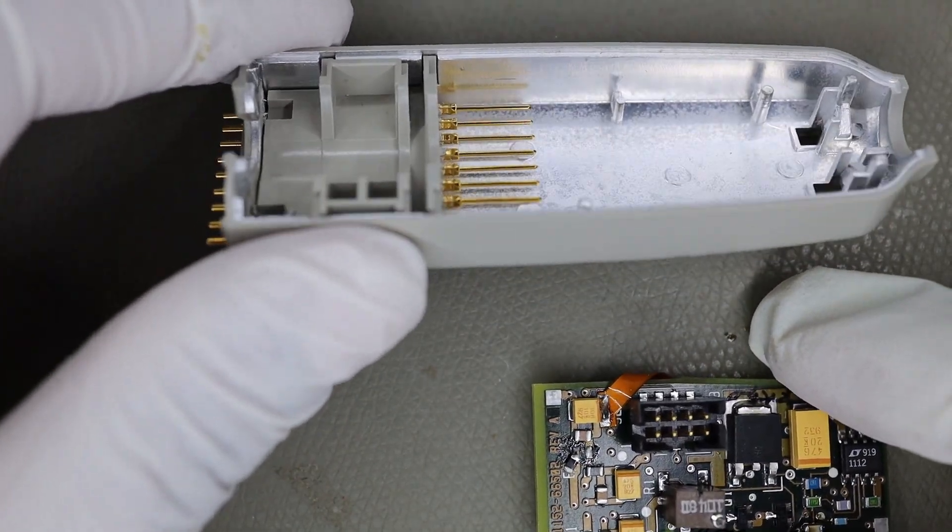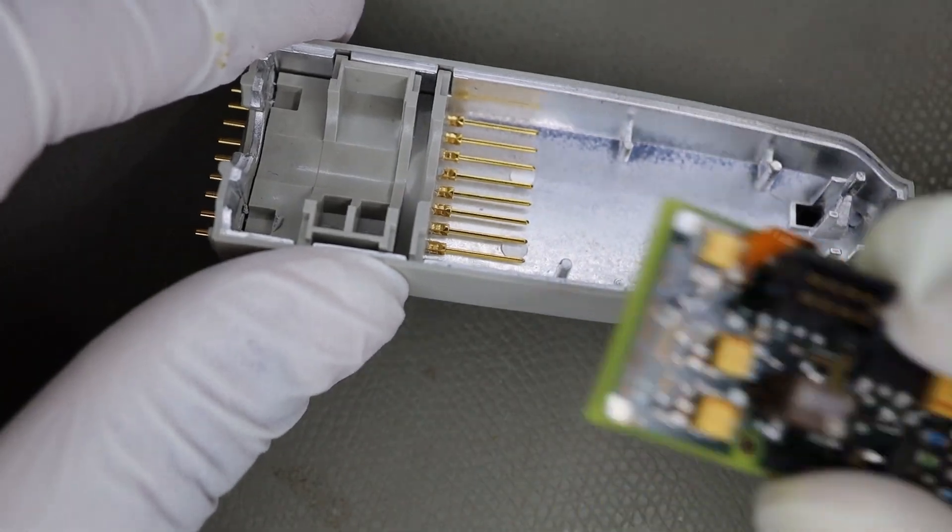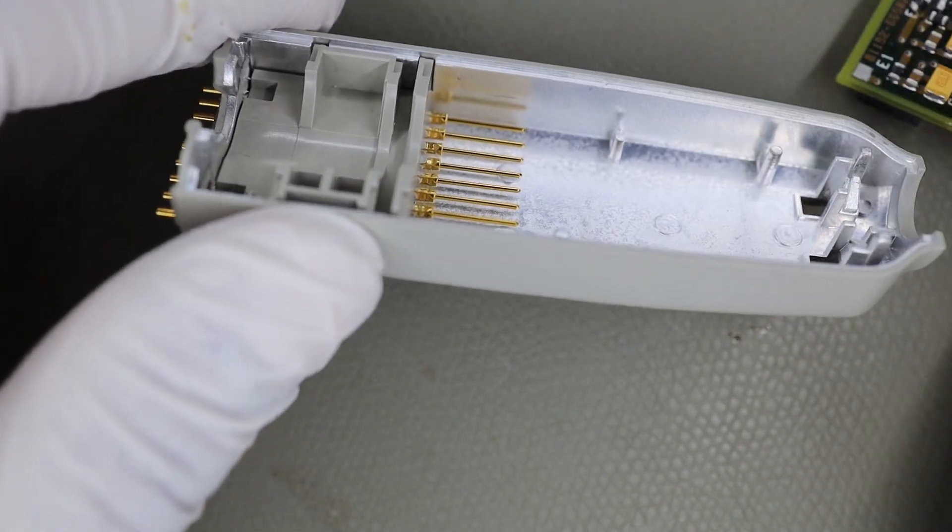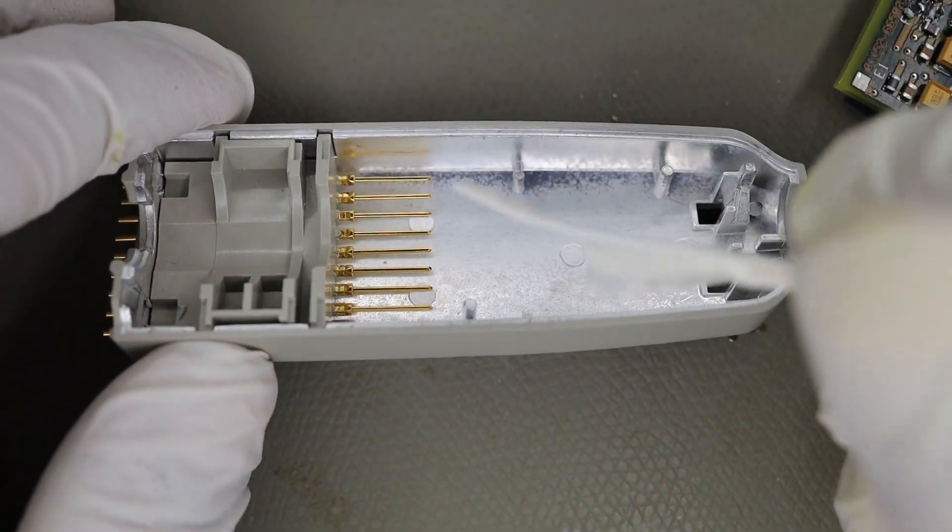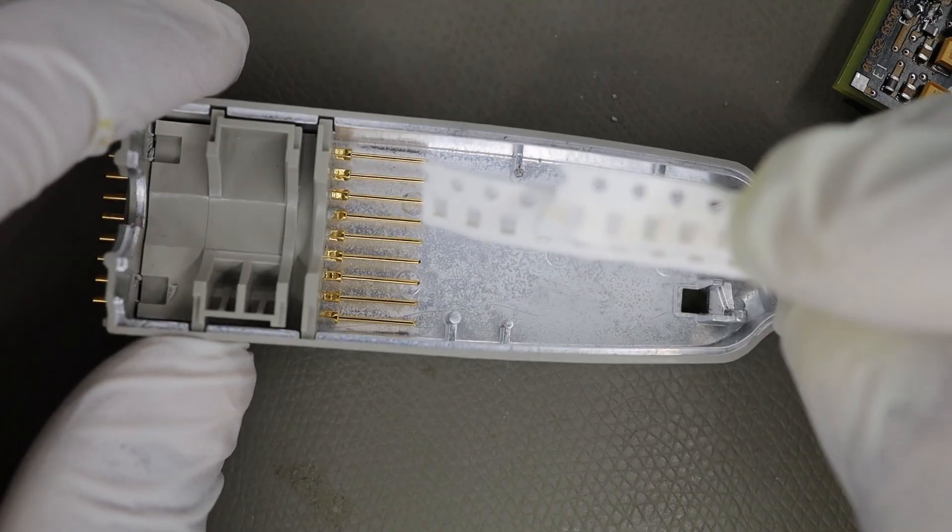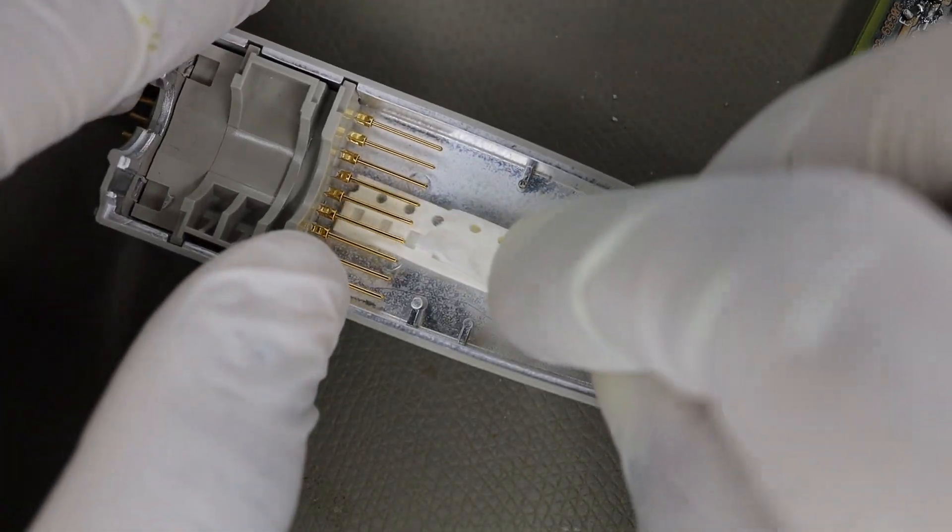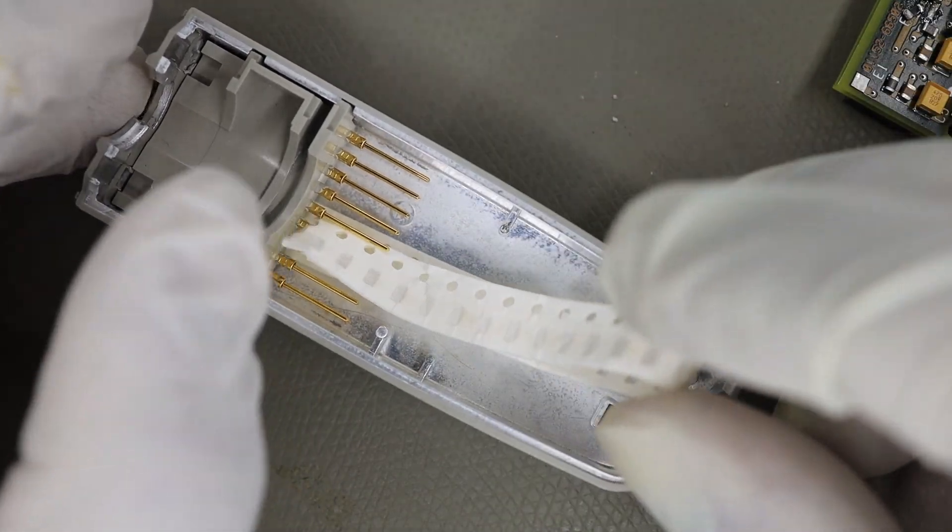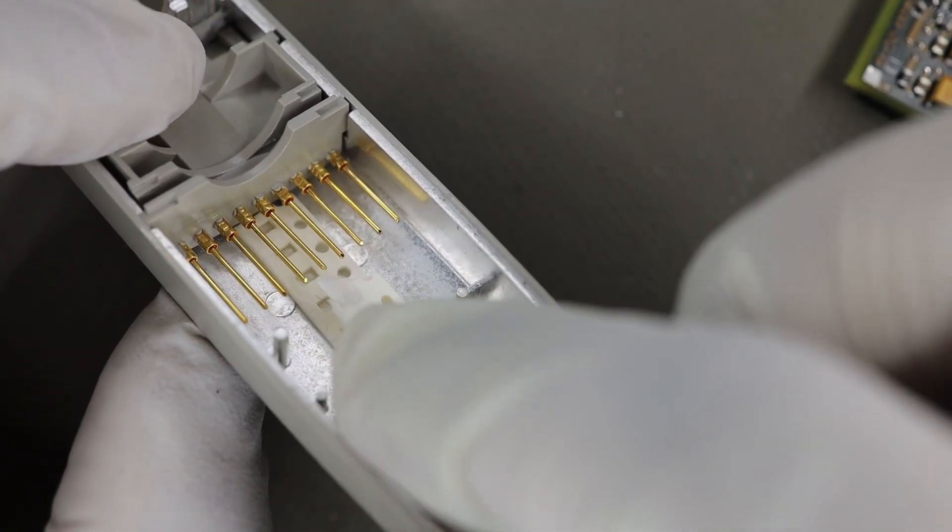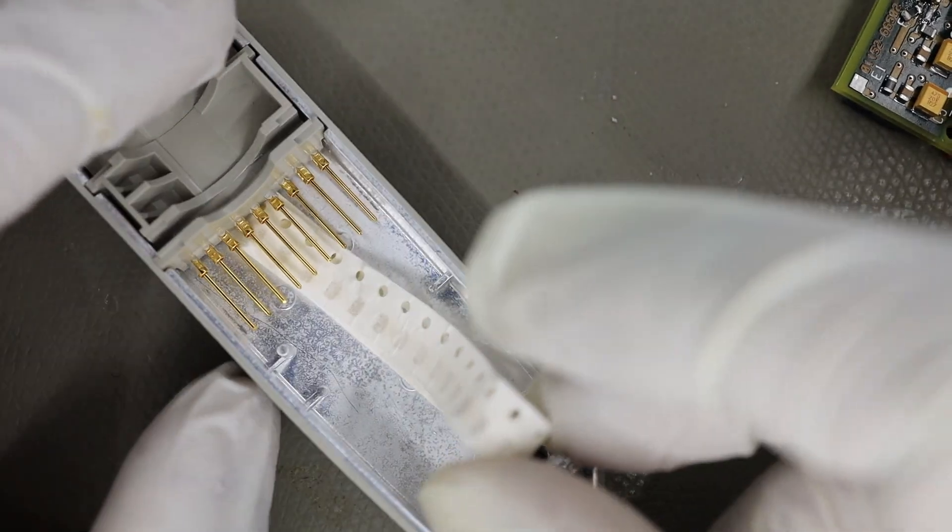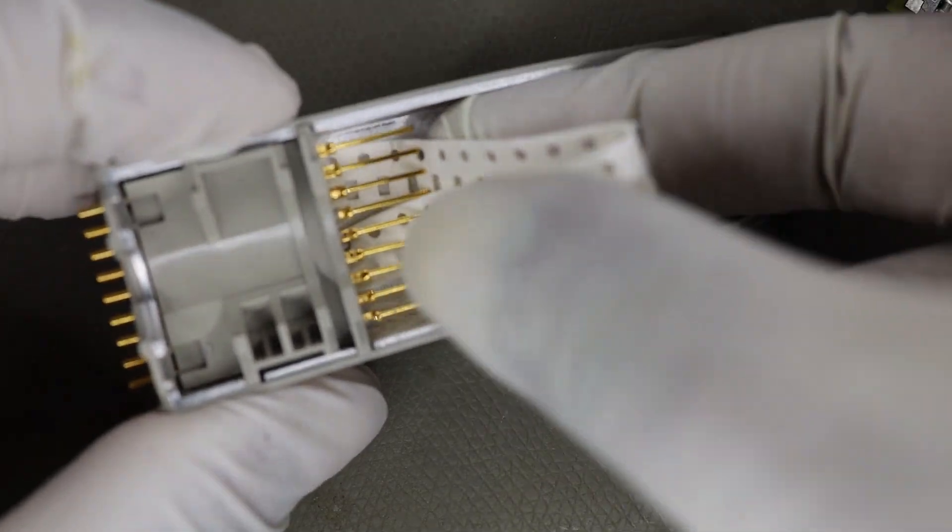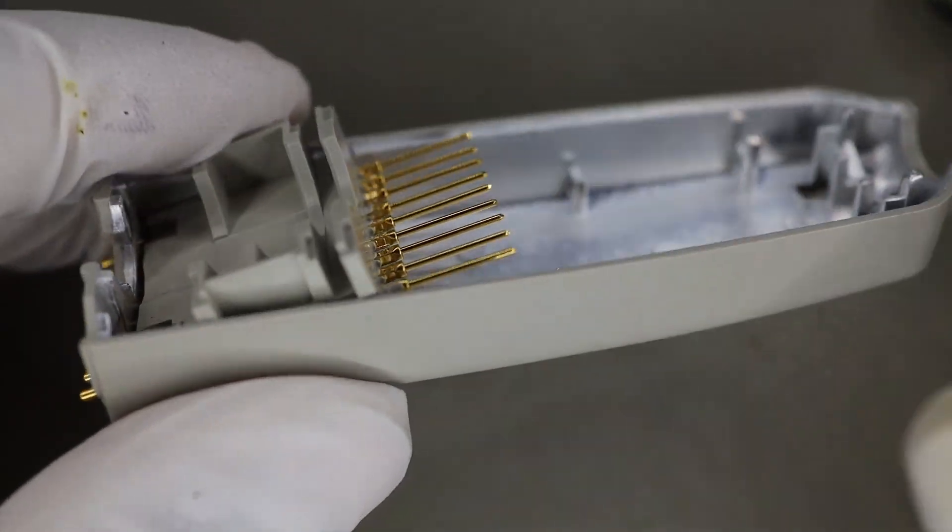Let's see how does it go back. If we look at this body, these pins are sitting way down there. You can never have it back because you have to flex all those pins. The solution to this problem, without scratching this metal surface because it's really thin - I have found this SMD tape to be pretty useful. What I will do is slowly slip this thing down between the body and the pogo pin part. It's hard to do on camera. And then I will try to lift it a little bit. This is the way it gets lifted.